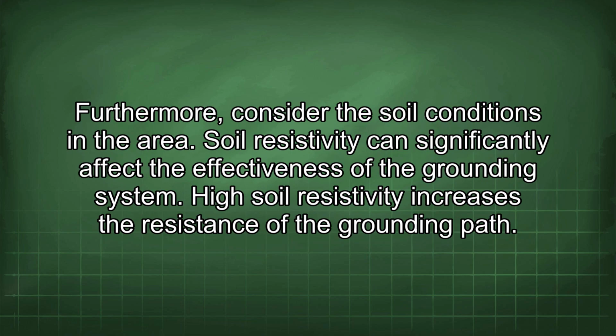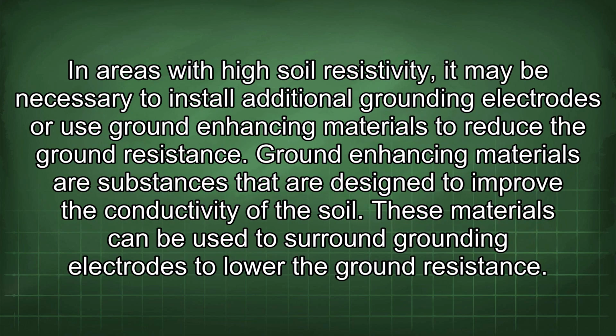Furthermore, consider the soil conditions in the area. Soil resistivity can significantly affect the effectiveness of the grounding system. High soil resistivity increases the resistance of the grounding path. In areas with high soil resistivity, it may be necessary to install additional grounding electrodes or use ground-enhancing materials to reduce the ground resistance.